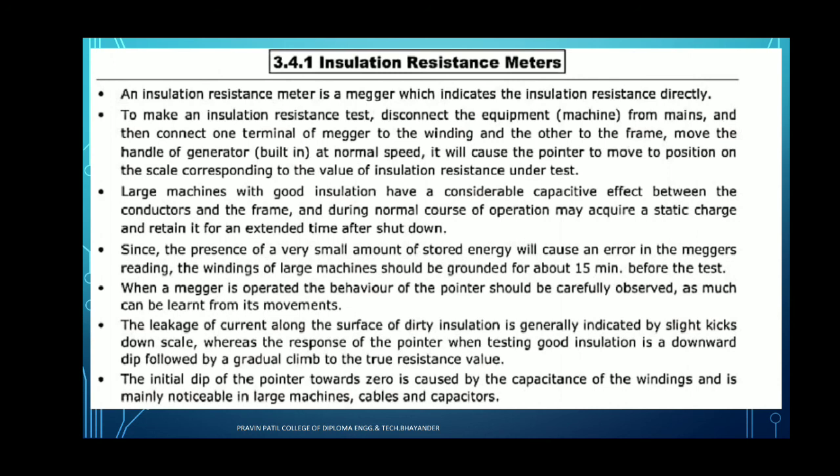When the megger is operated, the behavior of the pointer should be carefully observed. The leakage of the current along the surface of dirty insulation is generally indicated by a slight kick, whereas the response of the pointer when testing good insulation is downward. The initial dip of the pointer towards zero is caused by the capacitance of the different devices.